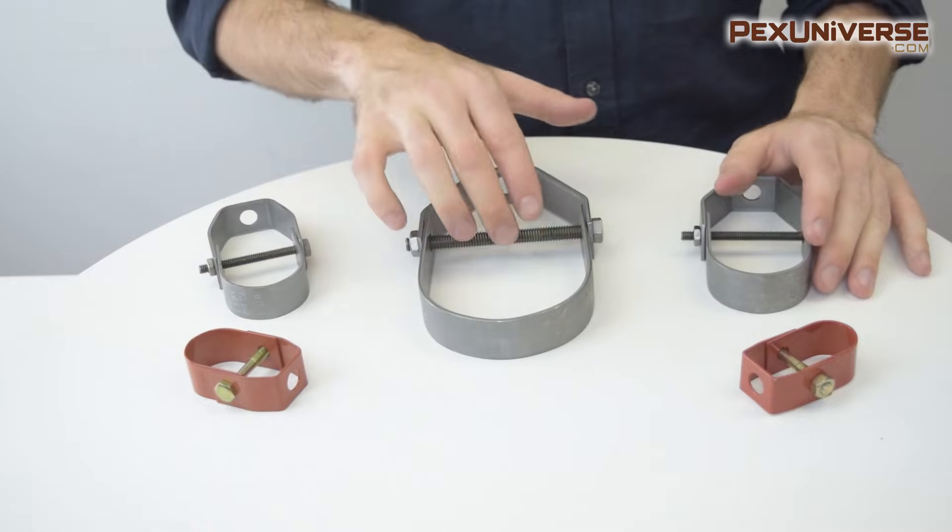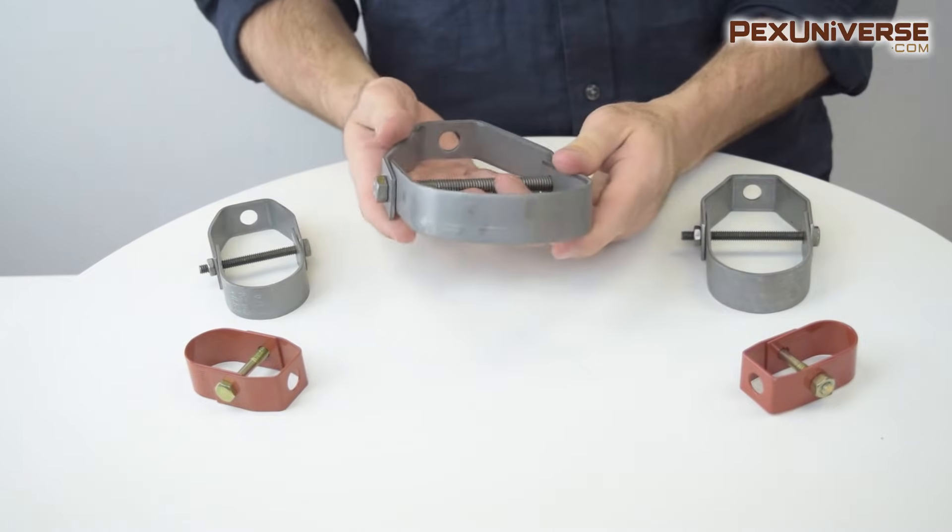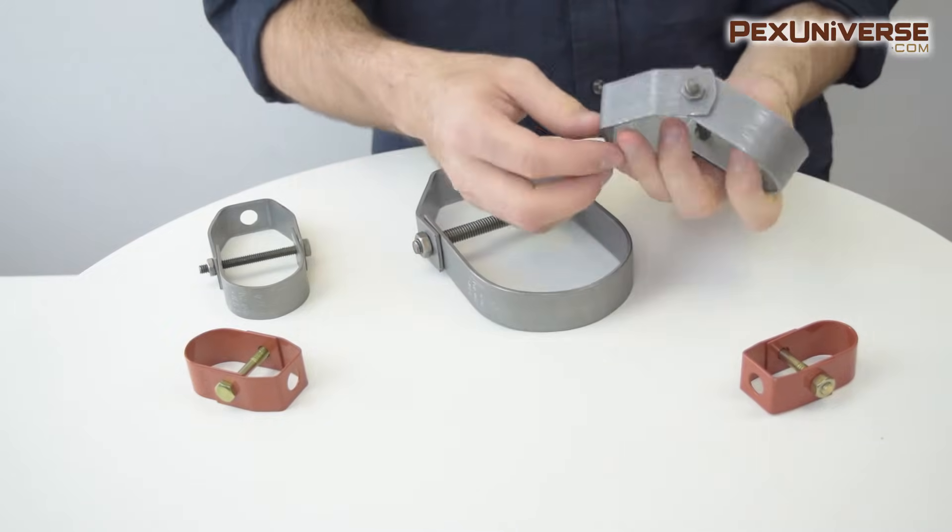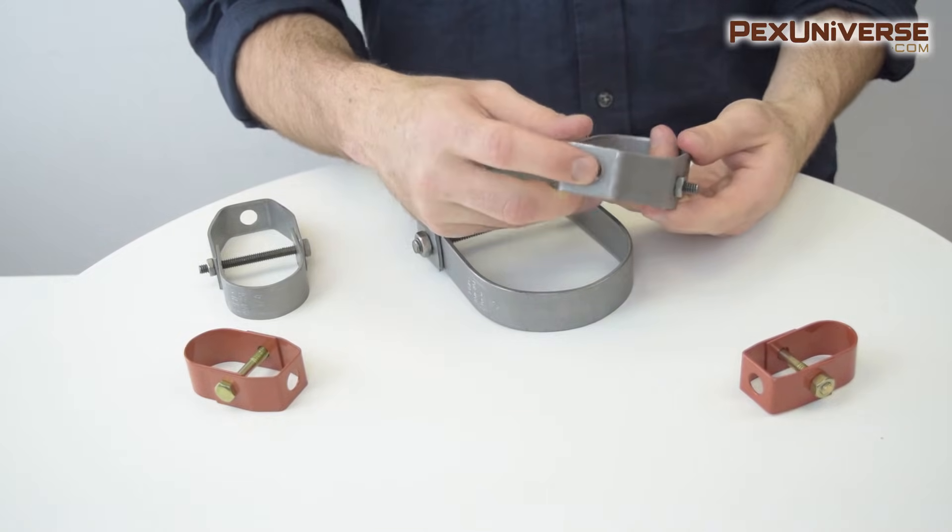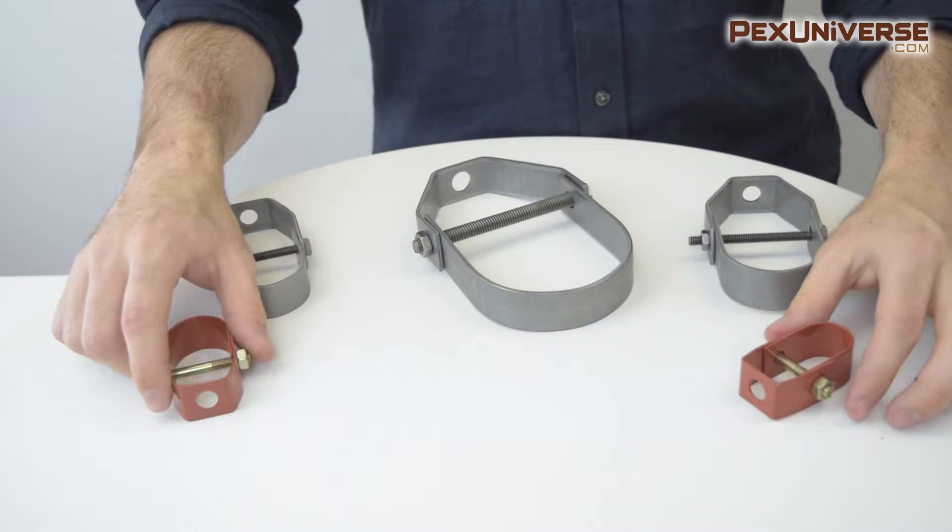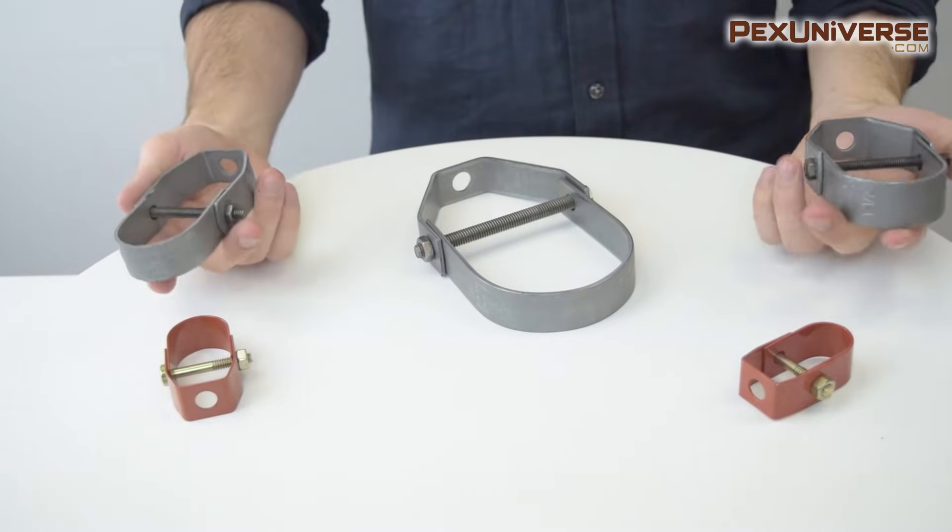This is the clevis hanger and it's used to support horizontal pipe runs most commonly near the ceiling. These are used in combination with threaded rod and beam clamps or ceiling plates. Various options are available for copper, black iron or cast iron, and PVC pipes.